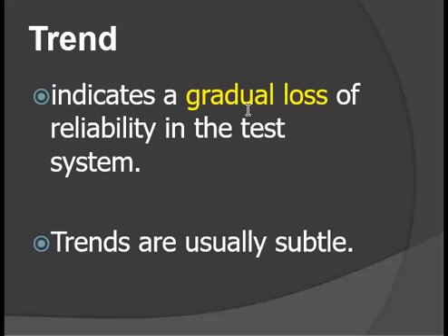Okay, so the trends occur when values gradually but continually they move in one direction. And same, when can you say that there is already a trend? When they are moving in one direction, for example, paakyat ba ng mean or pababa ba? They are moving in one direction and then you're again considering over 6 or more control runs.